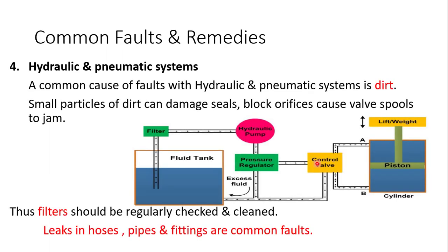Fine. So the filters are regularly checked and cleaned in this case, because in the pneumatic system, if dirt is accumulated inside the cylinder, it would get into your circuit. Clear? So this could damage your seals and block orifices. So this is a major problem related to the pneumatic system. In that case, you need to check the leaks, pipes, fittings, which are common faults. So what you need to check every time is to clean the air, fine, whenever it is getting into your cylinder.